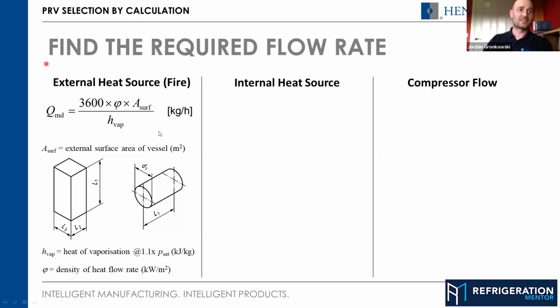So external fire, here's your equation for QMD. You've got the surface area of the vessel. If it's a simple tank, then it's straightforward enough. If we've got something like a condenser, you use the boxed area, if you like, rather than taking all the surface area of the fins. It doesn't work if you do that. HVAP is the heat of vaporization, which is taken at 1.1 times the set pressure. And then you've got the Greek letter phi, which is the density of heat flow rate. Again, that is given in the standard as 10, but it may vary if you've got things like insulation on the vessel.